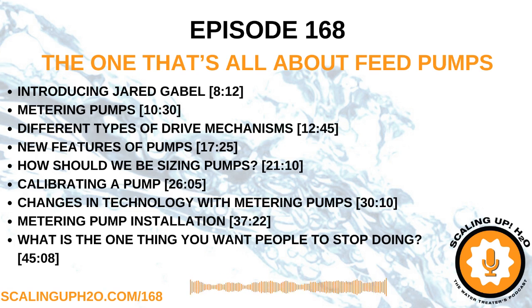So what we've noticed is that when you start injecting a chemical like sodium hypochlorite that wants to off-gas readily, if you don't use a 100% sweepable volume or 100% stroke length, you're basically taking that air bubble that gets trapped in there and just making it bigger and smaller and bigger and smaller and not actually moving chemistry. We're just taking a bubble and expanding it and contracting it. But if you have a pump that's able to always use 100% stroke length, then we can push those bubbles out. And there's a thing I'll say again, the sweepable volume. That's when the diaphragm moves from the back position all the way to the front position to move out as much of that volume as possible in that dosing head, which clears and mitigates that issue of vapor locking, which, if that happens, you have to go and reprime the pump.